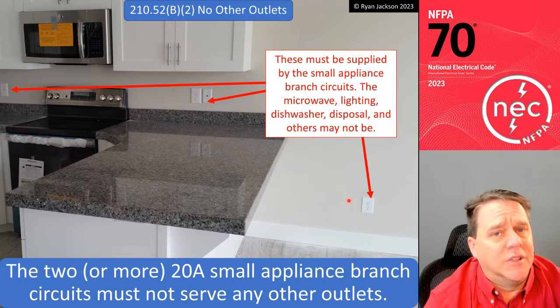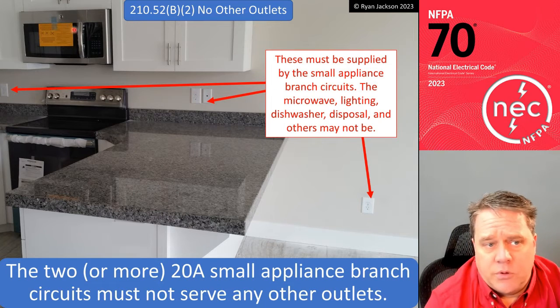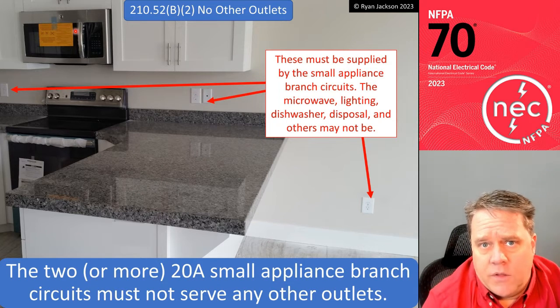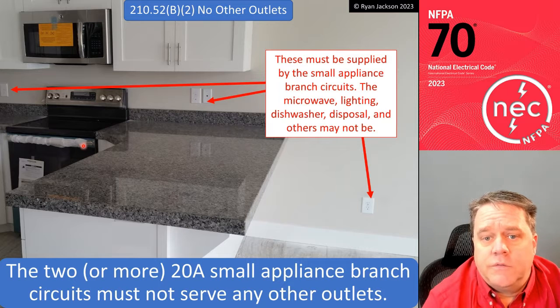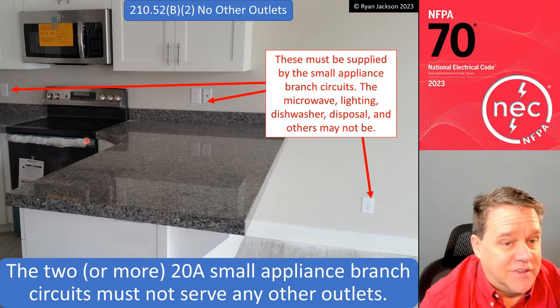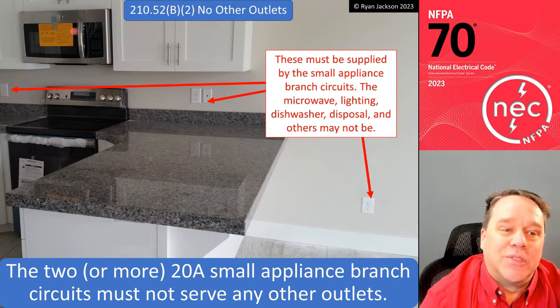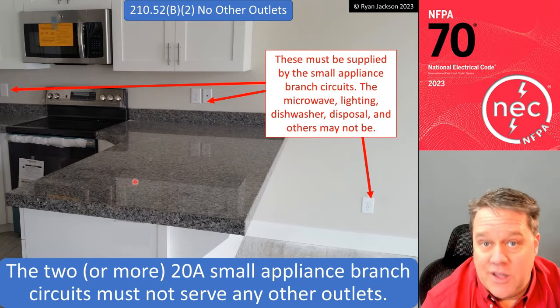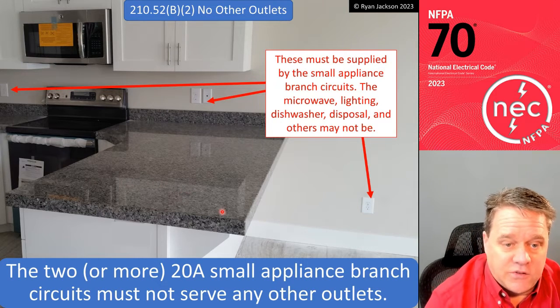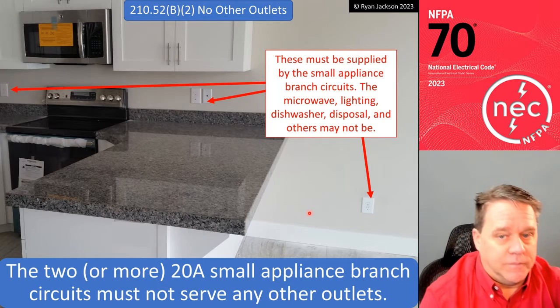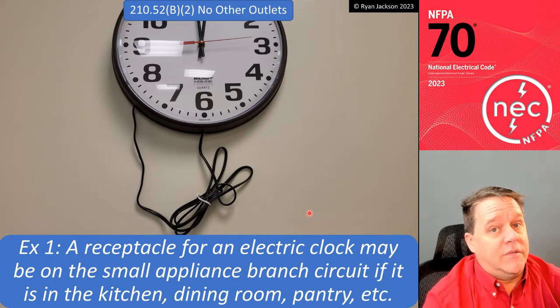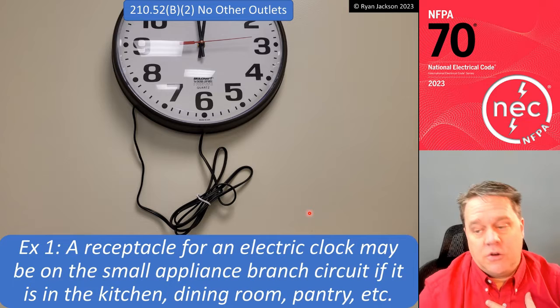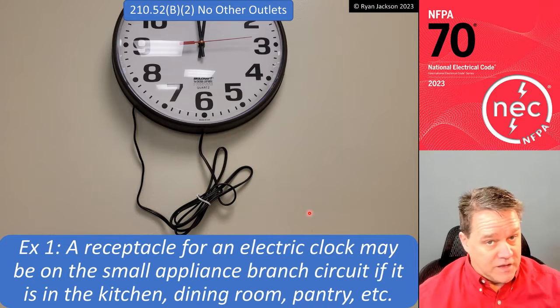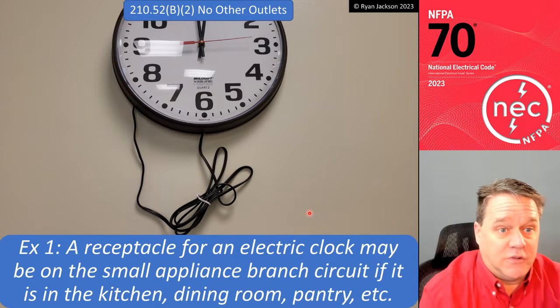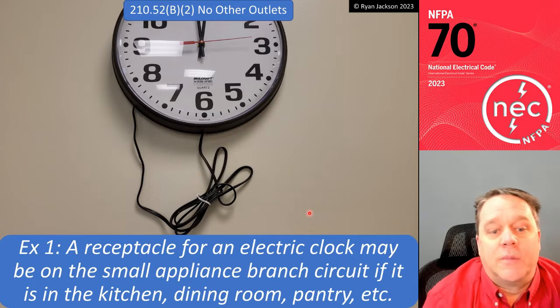You cannot put lights on this circuit. You cannot put the microwave on the circuit. You can't put the gas igniter. Well, the gas igniter actually has an exception. But you can't put the microwave, you can't put the dishwasher, you can't put the disposal. This is all that you can put on it. However, we do have an exception for an electric clock. Right? Thankfully, because I was wondering, like, where am I going to plug my clock? Yeah, okay, so receptacle for an electric clock.